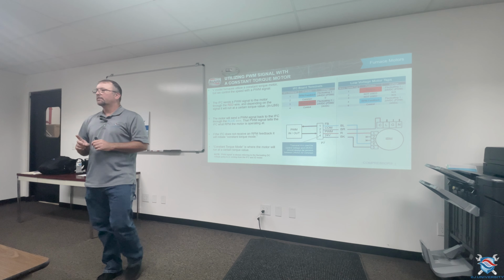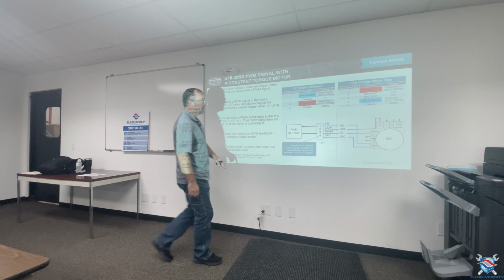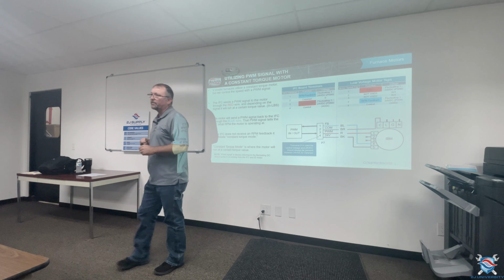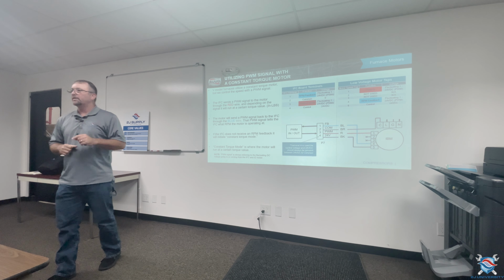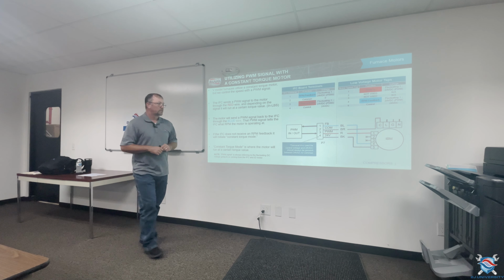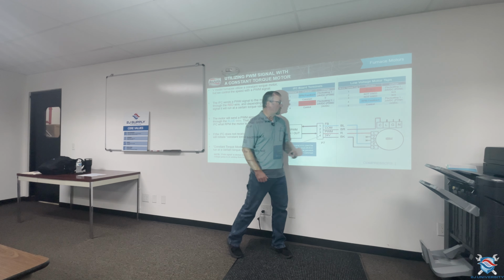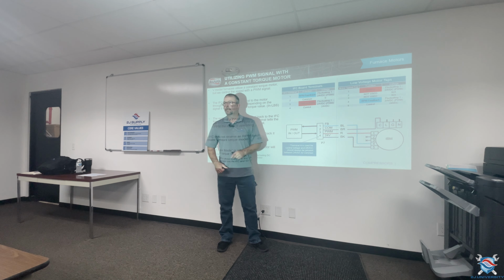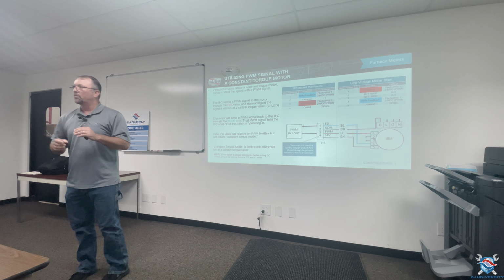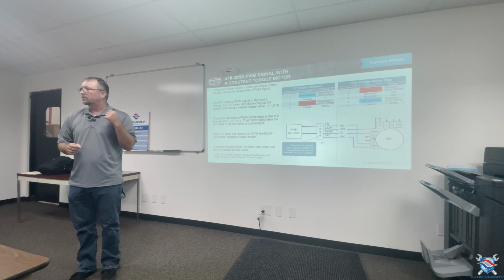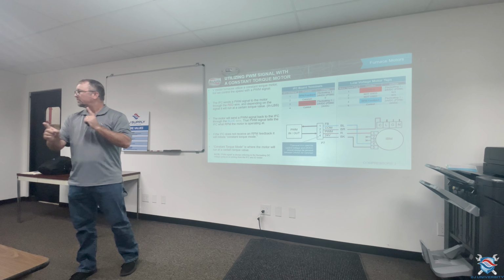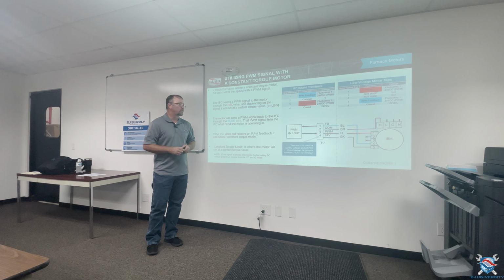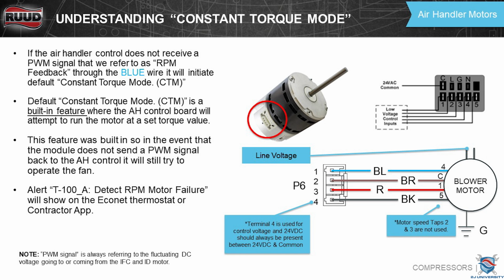It'll go to 100%. Basically what you're going to do is if for any reason you're having issues with this blower and you pull that feedback wire off, you've now turned it into a constant torque ECM motor. So what it does, this PWM signal sends a signal out to the blower from the control board, and then this feedback measures the RPM of what that blower's doing. So one's telling it what RPM it needs, the other one's telling the actual true RPM, and then it just continuously measures back and forth. But yes, great question. Once again, between 4 here and common, you're going to have 24 volts DC, constant.